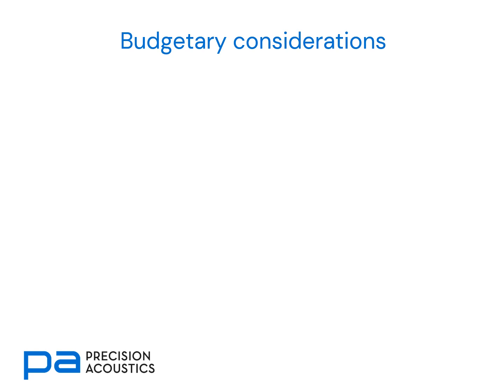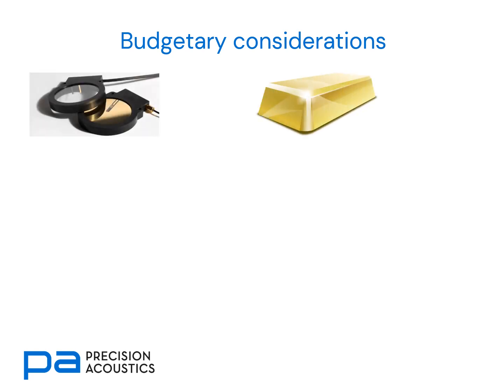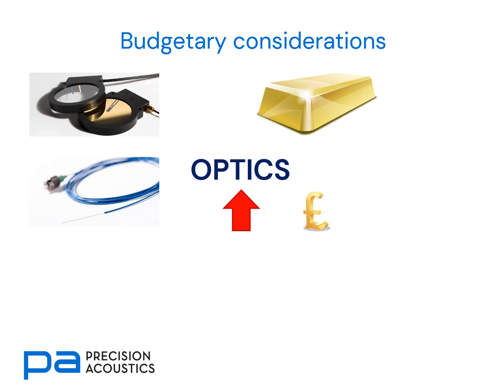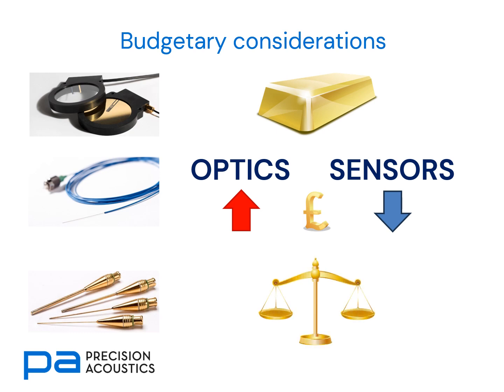It's important to consider budgetary considerations as well. A membrane hydrophone is a gold standard measuring device and is often reflected in its price point. Fibre optic sensors themselves are very cheap compared to other hydrophone types, but the optics needed to drive them can be somewhat more expensive, so one has to balance the consumption of sensors against the cost of the optics. Quite often, needle hydrophones provide the best balance between capability and cost.